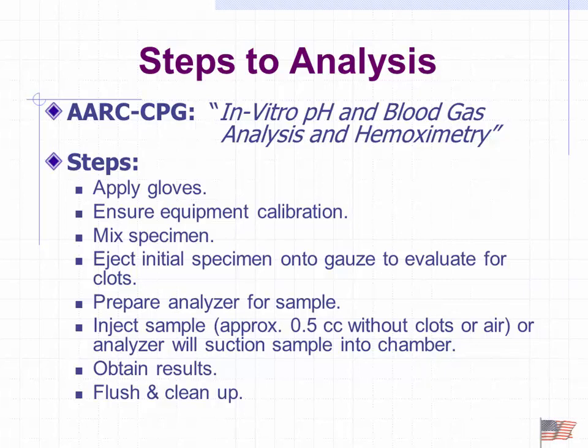Most blood gas analyzers don't require very much blood at all to do the actual analysis. We're going to sample somewhere on the order of 2 mLs, but it's going to only need really about a half a ml to actually do the sample. Get our results. We're going to flush the system once we're done, because we don't want that old stagnated blood that's sitting in there to remain in there. You want to flush it out into a waste bottle.